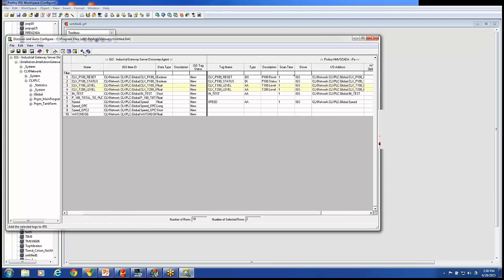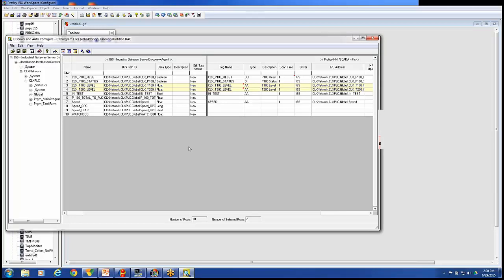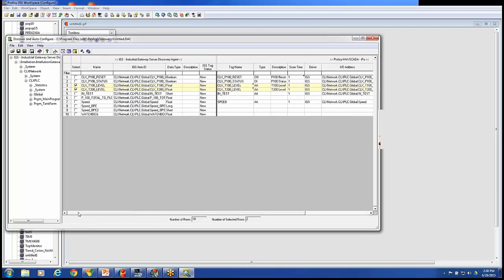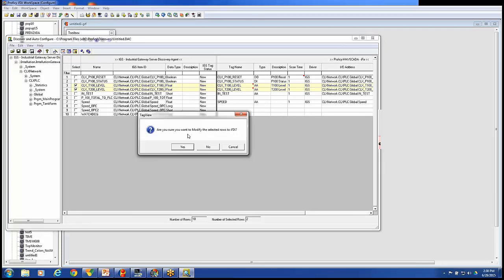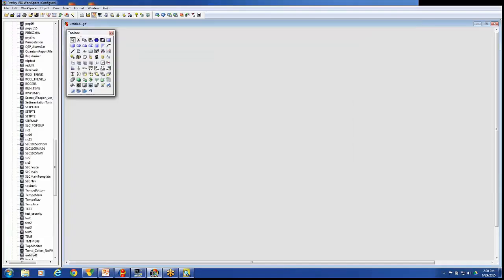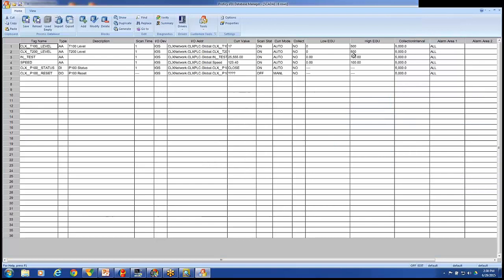If I click on Add to iFix, I'm actually going to get an error message. It tells me tag creation failed. It's because they already existed. But if I click on Modify, it will go out and will modify those tags in the iFix database. So we can go out here and see those are now set to 0 to 500. 0 to 500.